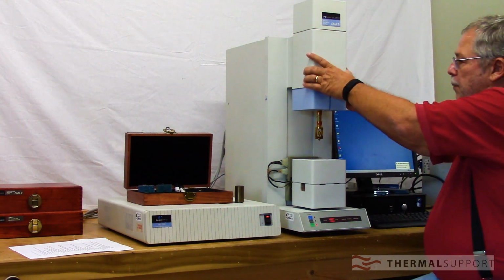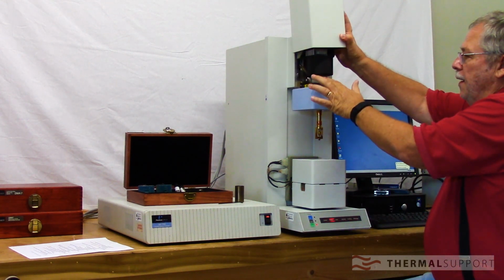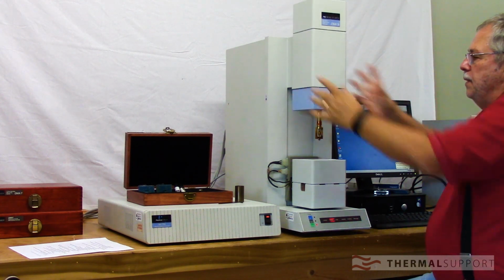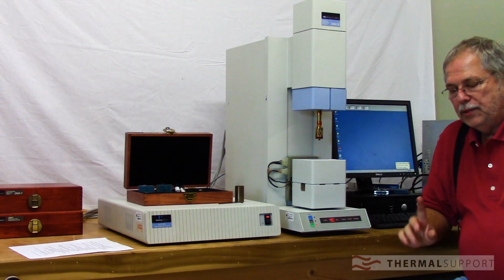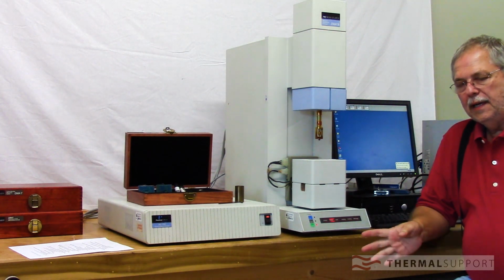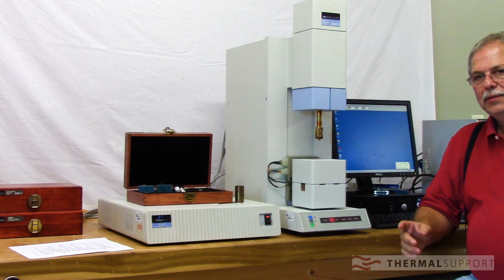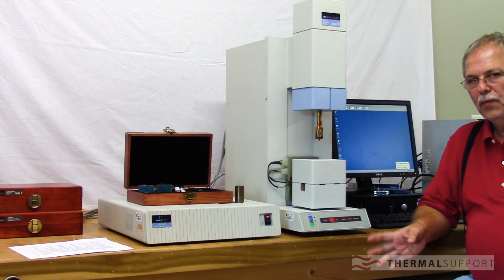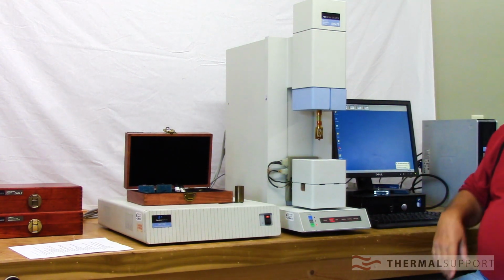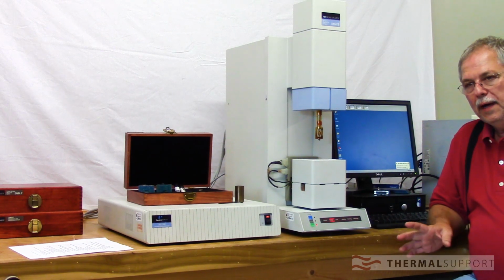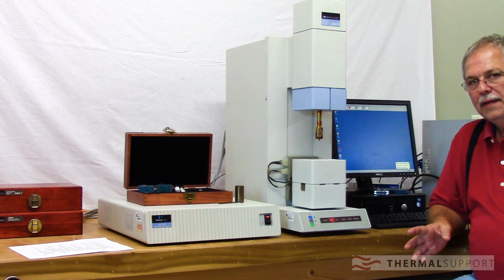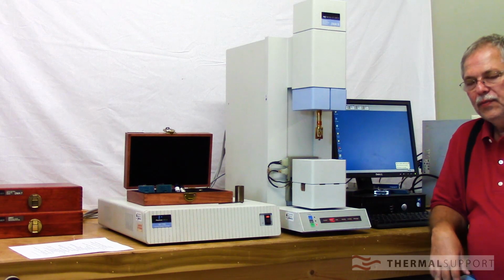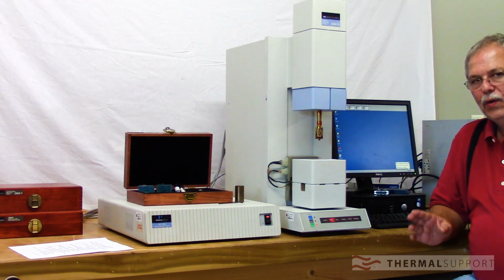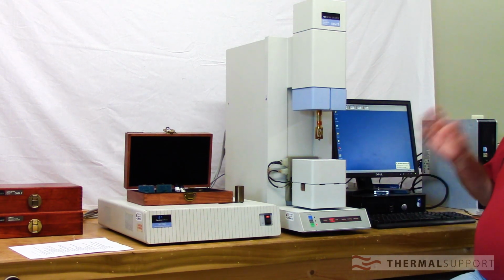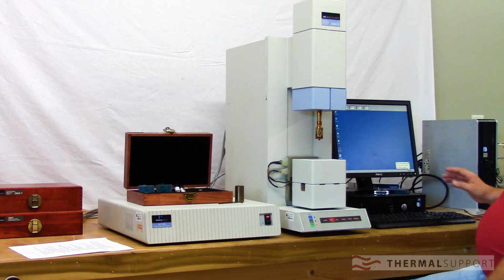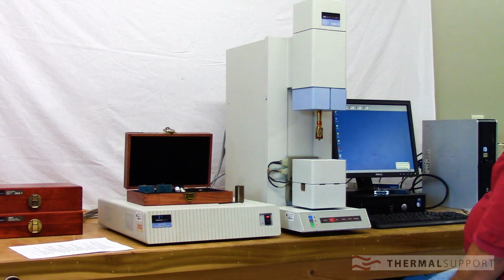So this is not warming up. You remember the LVDT power supply I showed you right here? Well, that right now is at room temperature. These analyzers go places where they have labs that are cold, and places where they have labs that are warm. Those two cartridge heaters are going to keep the LVDT power supply at 45 degrees centigrade. And that takes at least 45 minutes to equilibrate like it should.